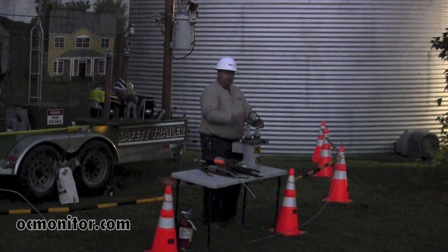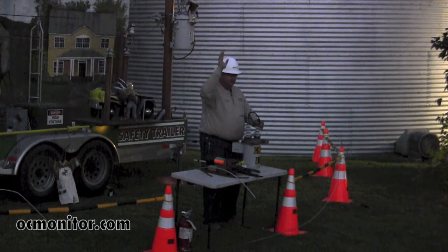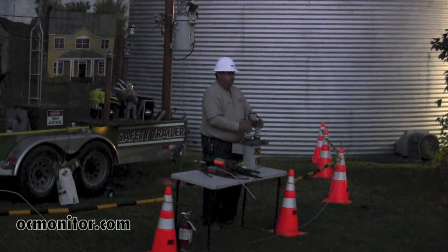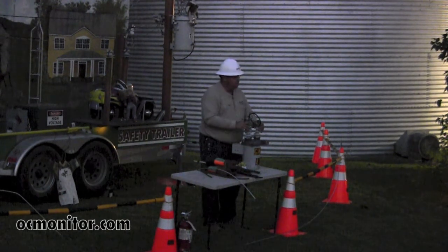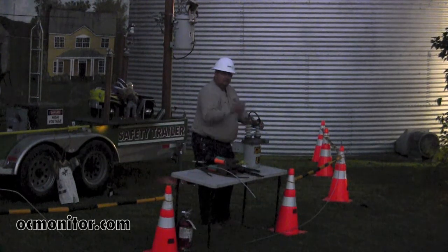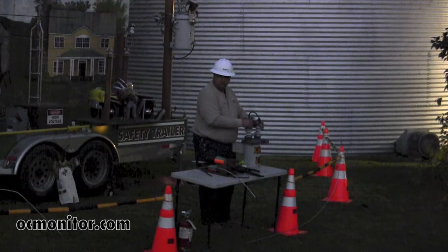Why is that important for you to know? If you have a generator hooked up in your home and you don't have a proper transfer switch or a proper disconnect, that can be very detrimental. A transformer doesn't care which way it transforms — the same thing can happen if you hook a generator up on your home. It comes back through the circuit, back to the transformers, and puts 7,000 volts back out onto the line to us. We do take precautions in storms — we test the line and we ground the line.